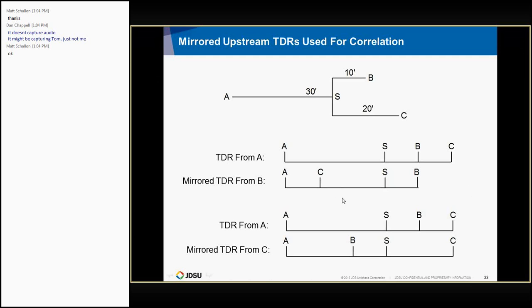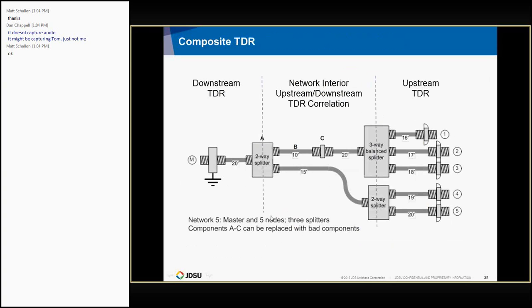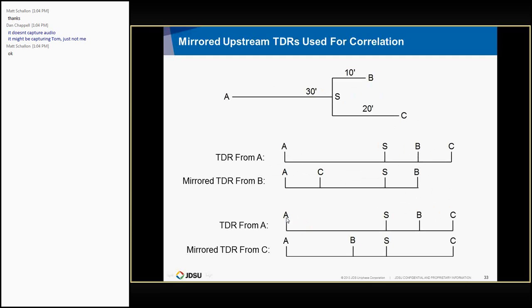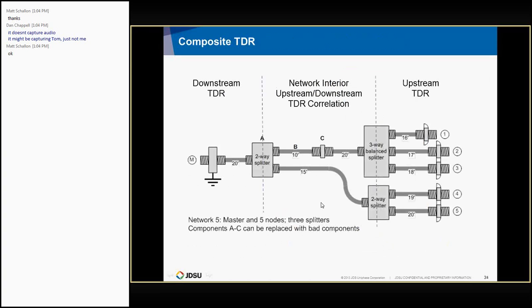Basically, what I'm doing is correlating the downstream sweep with the mirrored upstream sweep. And in the places where I have common reflections, then I know they're legitimate. But these reflections from other points downstream, which I don't want to see when I'm looking back from here, will be dropped out. And you see the same thing here. This is the mirrored TDR looking from C, and the B is going to be 10 feet this direction, looking downstream, and 10 feet this direction when you're looking upstream. And so when you correlate these two, you get rid of the extra reflection. So that's the key thing.